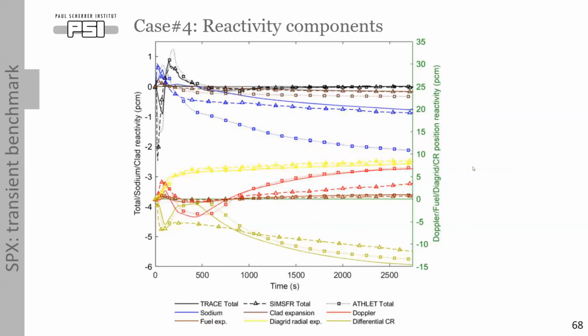So how complicated thermal expansion is - this light yellow or light green curve shows oscillations, and this is differential control rod. It includes vessel expansion, control rod drive line expansion, and diagrid expansion in combination.